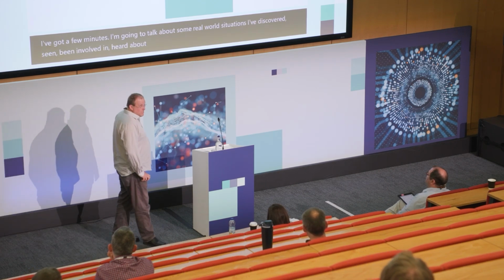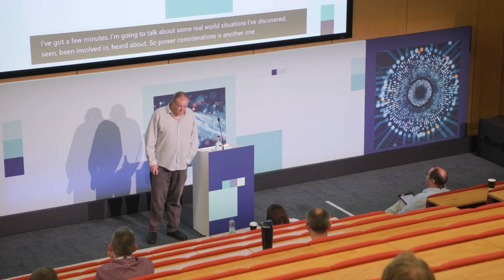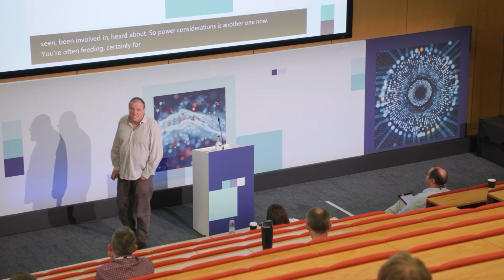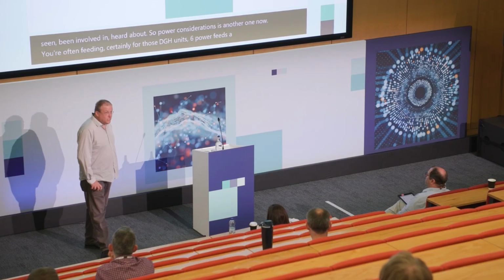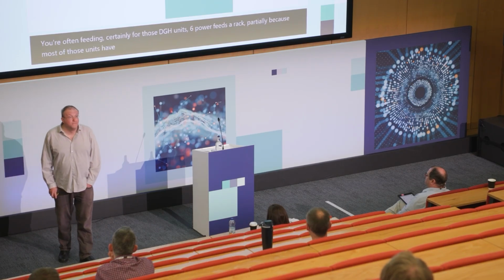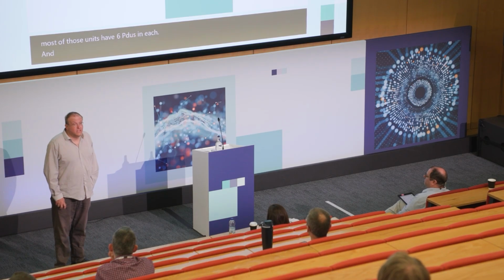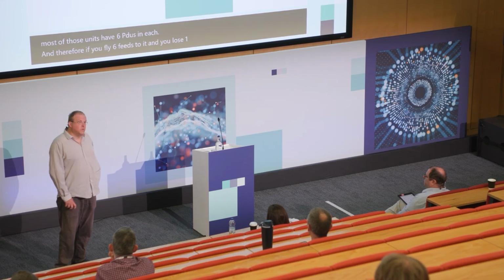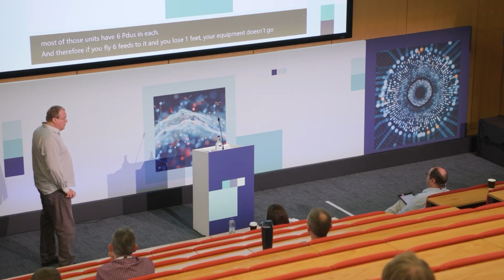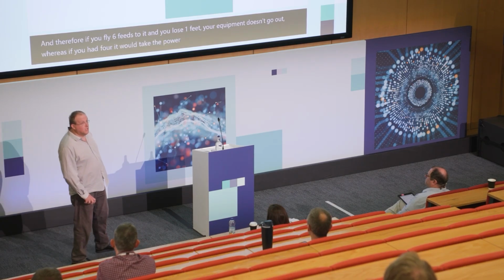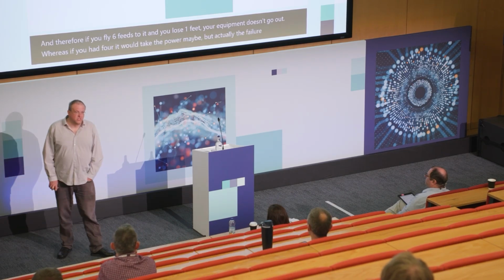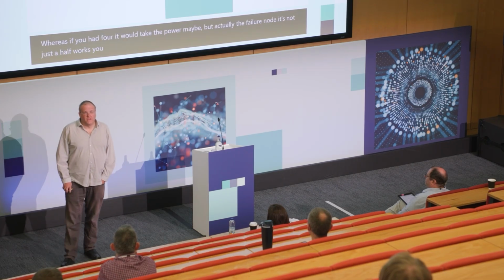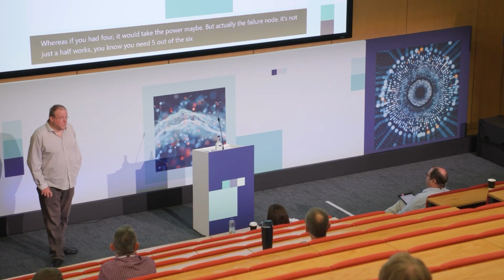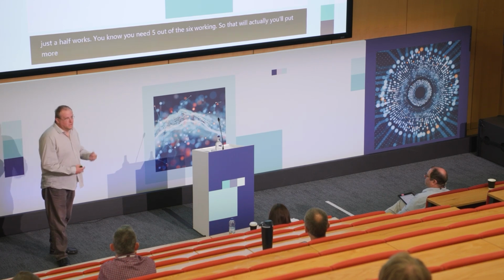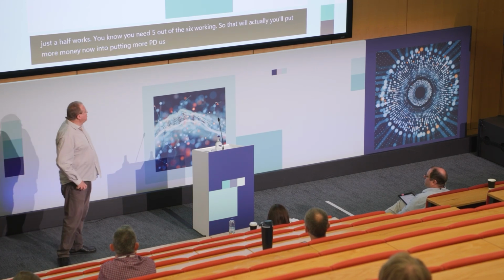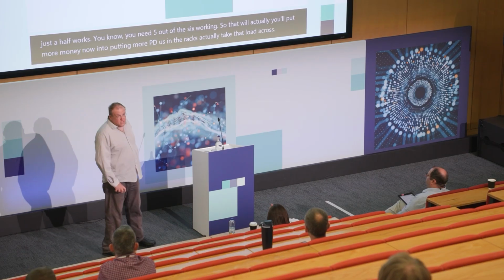I've got a few minutes to talk about some real world situations I've discovered, seen, been involved in, heard about. So power considerations is another one now. You're often feeding, certainly for those DGX units, 6 power feeds a rack, partially because most of those units have 6 PDUs in each. Therefore, if you fly 6 feeds to it and you lose one feed, your equipment doesn't go out. Whereas if you had 4, it would take the power maybe, but in a failure mode it's not just a half work, you need 5 out of the 6 working. So you'll put more money now into putting more PDUs in the racks to take that load across. They'll often be single phase, 32 amps.